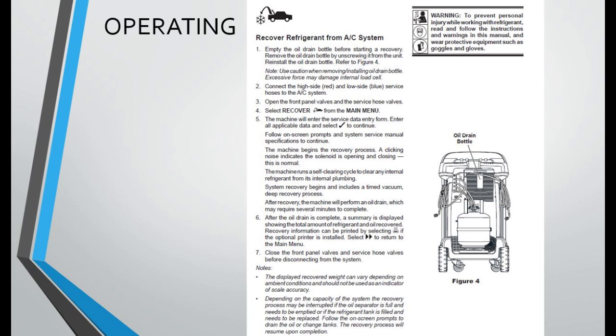2. Connect the high side red and low side blue service hoses to the AC system. 3. Open the front panel valves and the service hose valves. 4. Select Recover from the main menu. 5. The machine will enter the service data entry form. Enter all applicable data, and select to continue. Follow on-screen prompts and system service manual specifications to continue. The machine begins the recovery process.